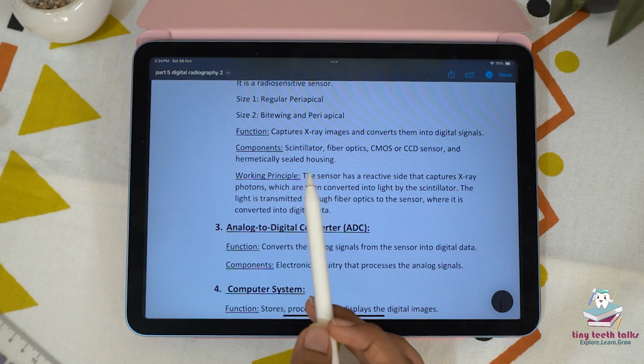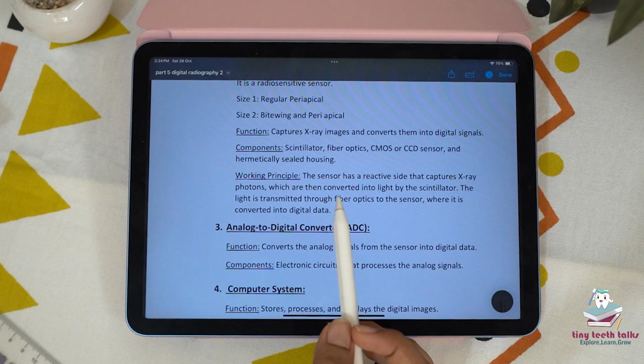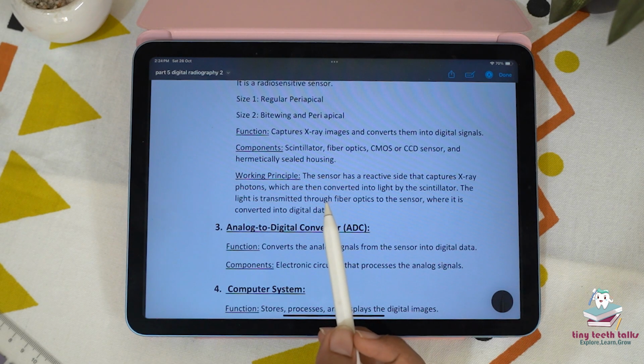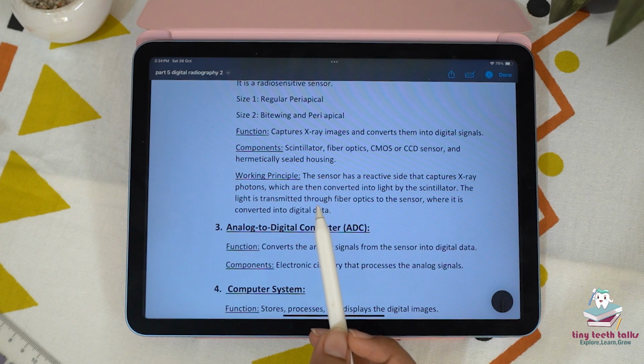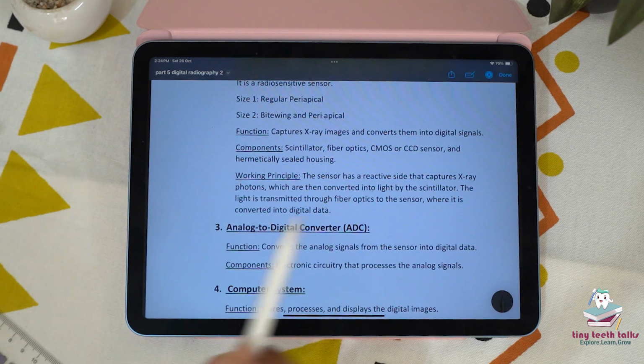So the scintillator converts the X-ray photons into visible light photons. It is essential for creating an image that the sensor can detect, since X-rays themselves are not directly visible. It works on the principle that when X-rays hit the scintillator material, it emits light in proportion to the X-ray exposure. Then the second is the fiber optics.